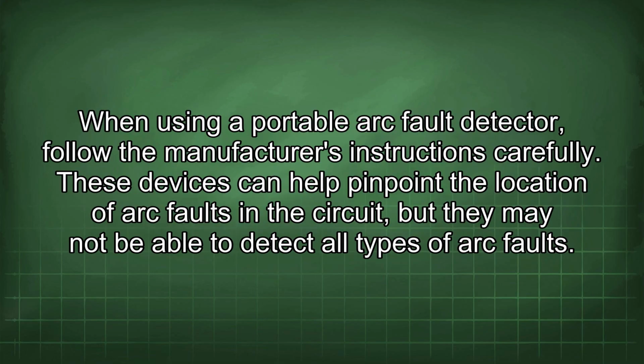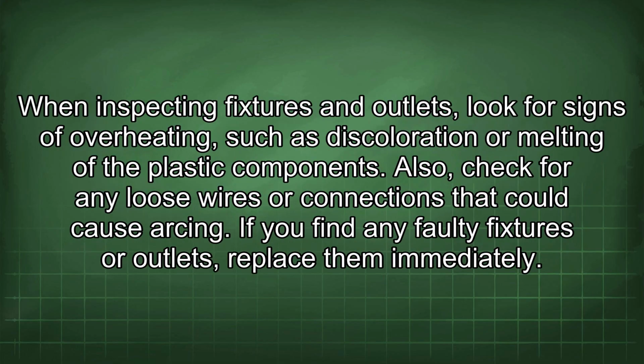When using a portable arc fault detector, follow the manufacturer's instructions carefully. These devices can help pinpoint the location of arc faults in the circuit, but they may not be able to detect all types of arc faults. When inspecting fixtures and outlets, look for signs of overheating, such as discoloration or melting of the plastic components. Also, check for any loose wires or connections that could cause arcing. If you find any faulty fixtures or outlets, replace them immediately.